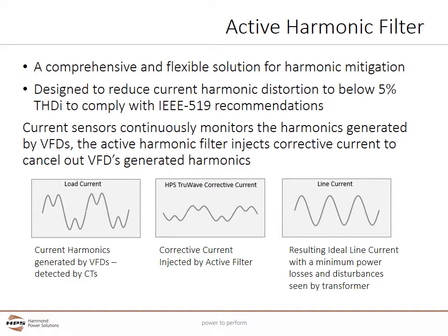Active harmonic filters use current sensors to continuously monitor the harmonics generated by variable frequency drives. The active harmonic filter injects corrective current that is equal to but opposite in phase to cancel out the VFD's generated current harmonics. The pictures at the bottom of the page show how this current injection and correction works to cancel out the harmonics.